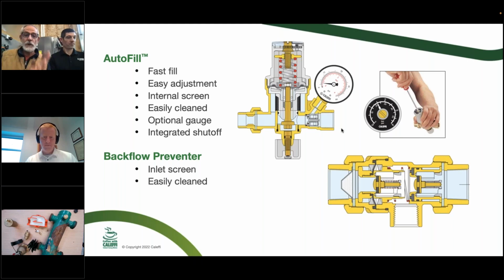We've heard some people say, well, they just put a swing check upstream of this backflow preventer, and the swing check will take the hit from the pressure spike and it won't hit the separator. Now you've got 3 check valves in a row, but if that's what it takes, I guess. Got to do what you got to do. Yeah.